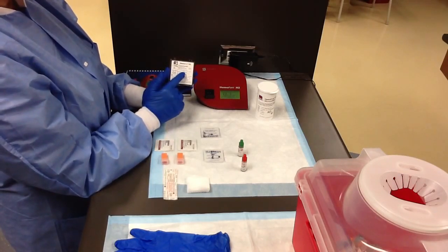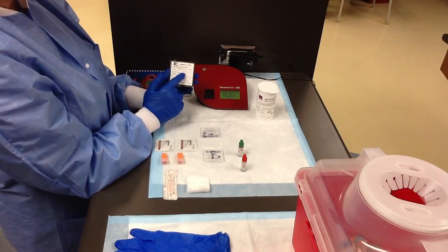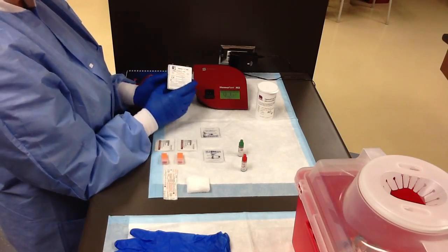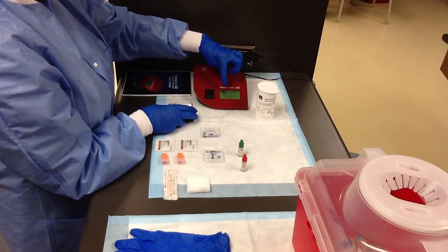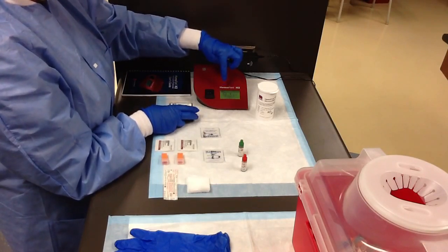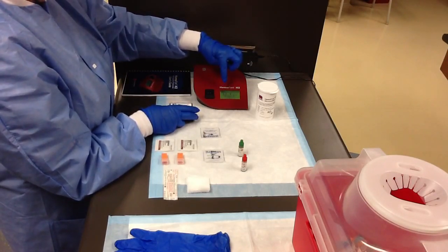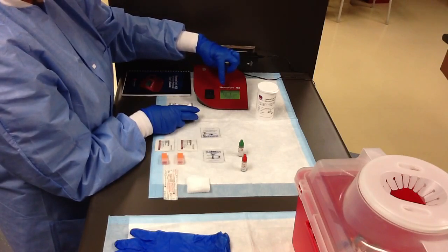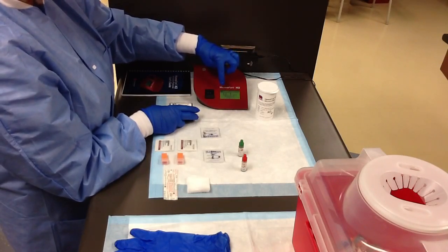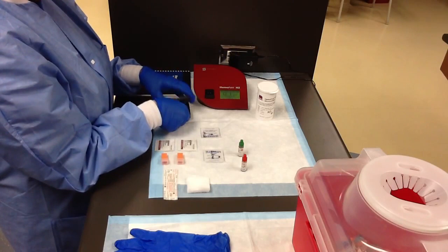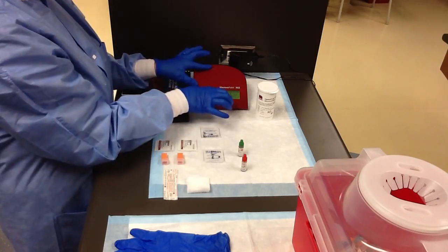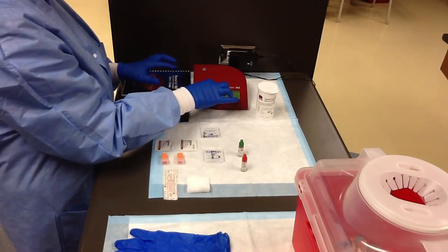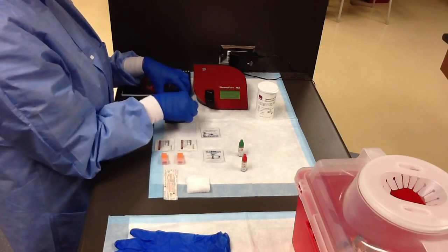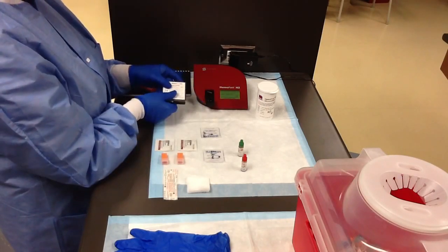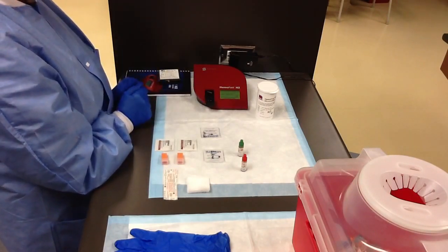The value on this container is 12.1 grams per deciliter, and the value found by the machine is also 12.1 grams per deciliter. So that tells us that the machine calibration is performed correctly and the machine is functioning correctly. Gently pull out the cuvette holder, replace the control cuvette in your container, and set it aside.